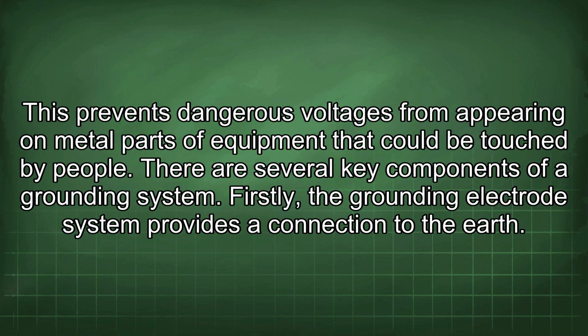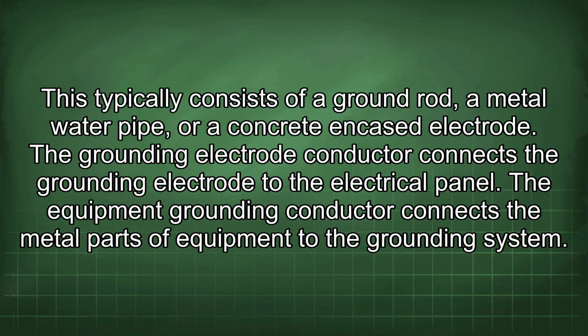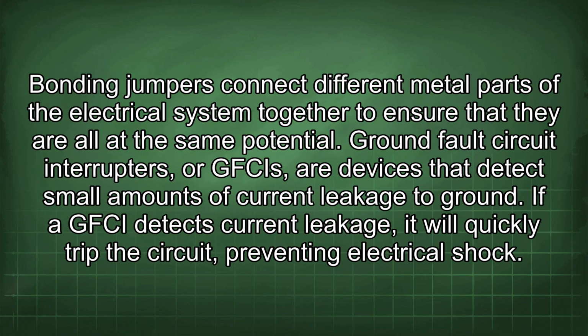Firstly, the grounding electrode system provides a connection to the earth. This typically consists of a ground rod, a metal water pipe, or a concrete encased electrode. The grounding electrode conductor connects the grounding electrode to the electrical panel. The equipment grounding conductor connects the metal parts of equipment to the grounding system.